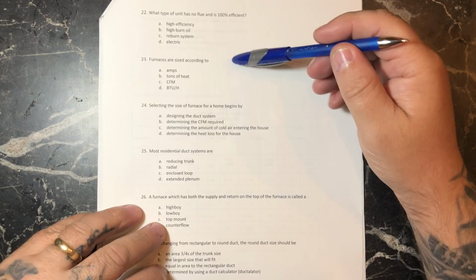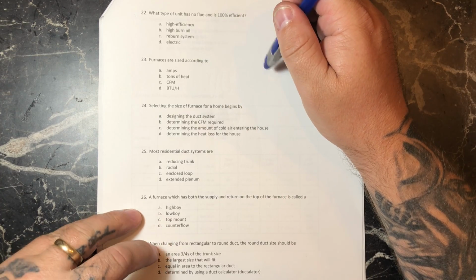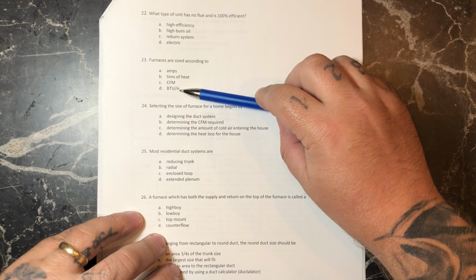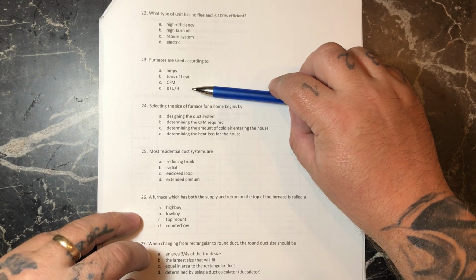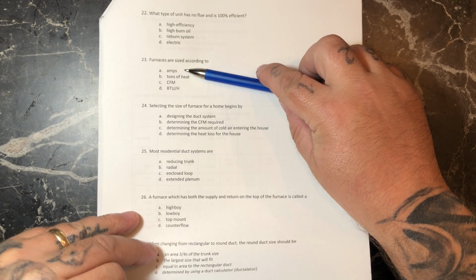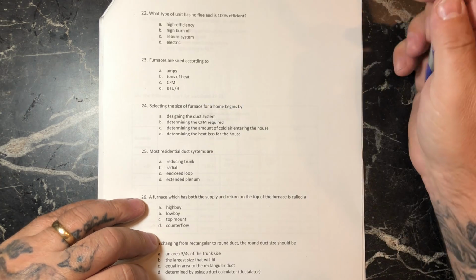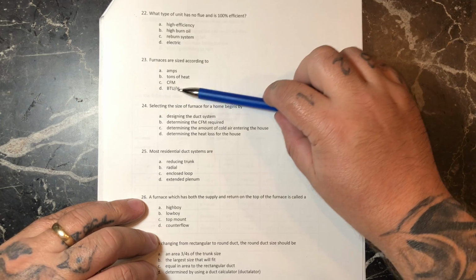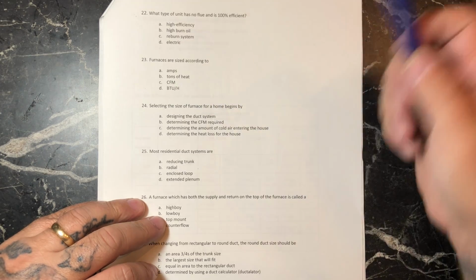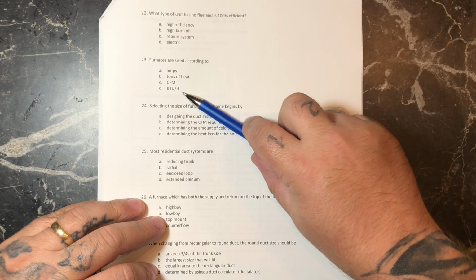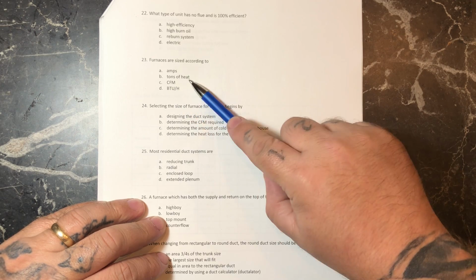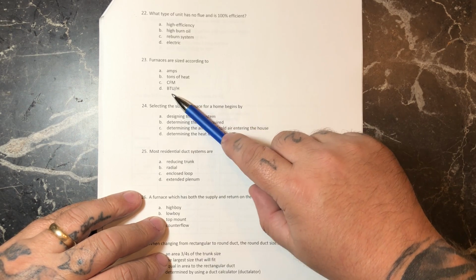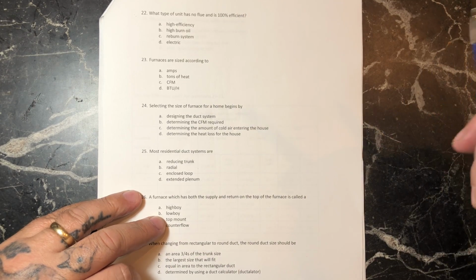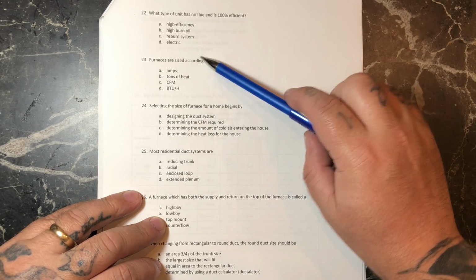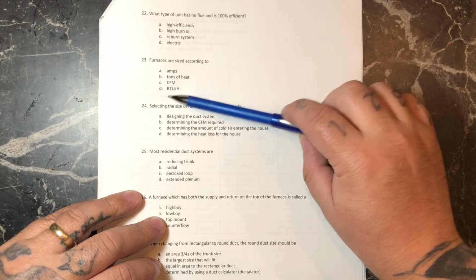So furnaces are sized according to BTUs. You know, this one has amps, tons of heat, CFM, and BTUs. Furnaces are going to be sized according to BTUs per hour, because that's how the heat loss and heat gain calculations are done. And then if it's a heat pump or something like that, it would be converted to tons of heat, or if it's electric, you'd convert it to amps or watts. But it's definitely going to be BTUs.